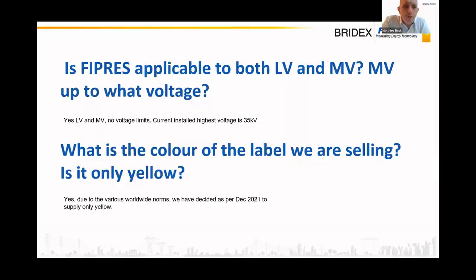So one common question that is asked is: is FIPRES applicable to both low voltage and medium voltage, and if medium voltage, up to what voltage? So yes, FIPRES is applicable to low voltage and medium voltage switchgear or panels with theoretically no voltage limit, but currently our highest installation is 35 kV.